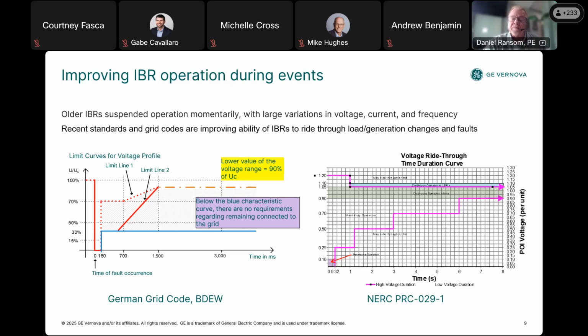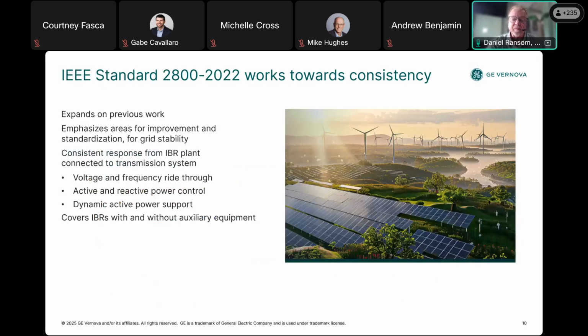At the bottom is the permissive operation region at less than 0.1 per unit. Here, the IBR plant may continue to exchange current with the transmission system, or it may operate in current blocking mode. It can shut down, but it's got to be on at least, in this case, 320 milliseconds. That's forever in relay time, so that will help the protection systems operate. The goal here is to avoid service interruption and poor power quality by maintaining the power system synchronous inertia and supporting protection schemes.